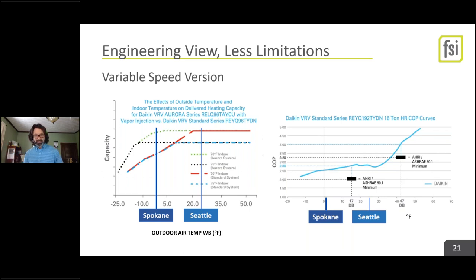So, okay, hang on. You were doing an engineering thing there, and could you just, at least for those of us non-engineers on the call, say what the two axes on each of these diagrams are, and what's the difference between them? Oh, sure. I guess I can. So the axis on the left-hand slide is capacity versus temperature. So temperature on the X axis and capacity on the Y axis. So you've heard this, it's gospel. Capacity drops as the temperature drops. And that's true because it's harder to get that heat out of the air. But look, that for this system doesn't really drop off until 12 degrees.